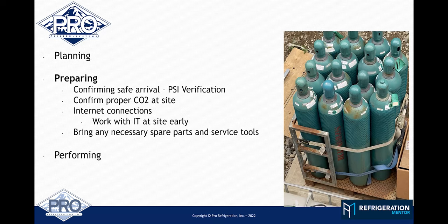With CO2 systems, you've got a couple different things beyond any refrigeration technician's bag. Make sure you've got a way to connect to your CO2 bottles. You can get those fittings from gas suppliers, the welding gas suppliers and places where you'd get CO2. When I started telling them that I'm not going to hook a regulator to the bottle because I'm using my transcritical gauges as the regulator, it surprises them to hear that. They say, no, we just need that connection right on there.